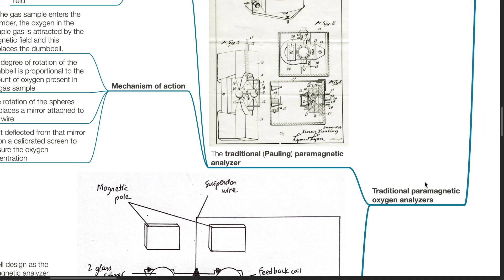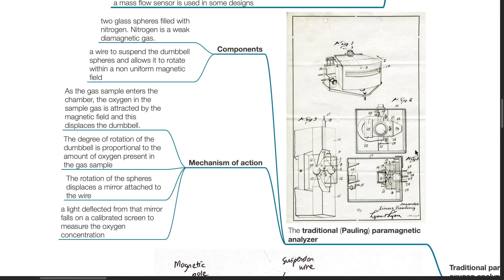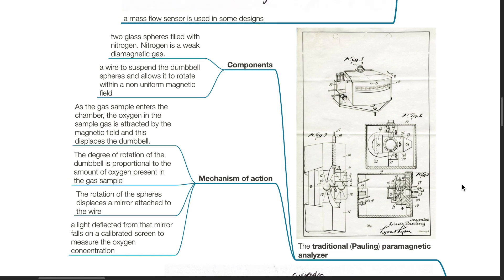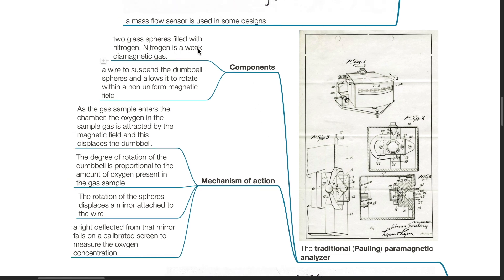The traditional Pauling paramagnetic analyzer has components including two glass spheres filled with nitrogen — a weak diamagnetic gas — suspended by a wire allowing them to rotate as a dumbbell within a non-uniform magnetic field. As the gas sample enters the chamber, oxygen in the sample is attracted by the magnetic field, displacing the dumbbell. The degree of rotation is proportional to the amount of oxygen present. The rotation displaces a mirror attached to the wire, and a light deflected from that mirror falls on a calibrated screen to measure the oxygen concentration.